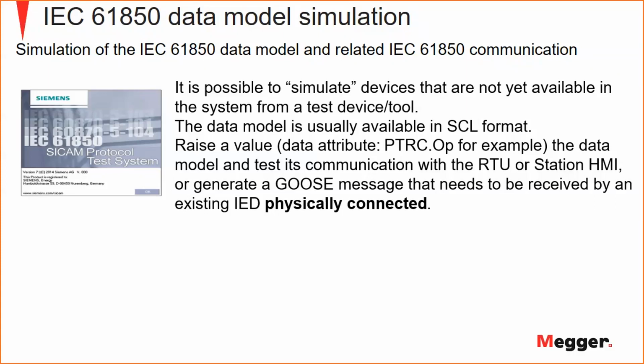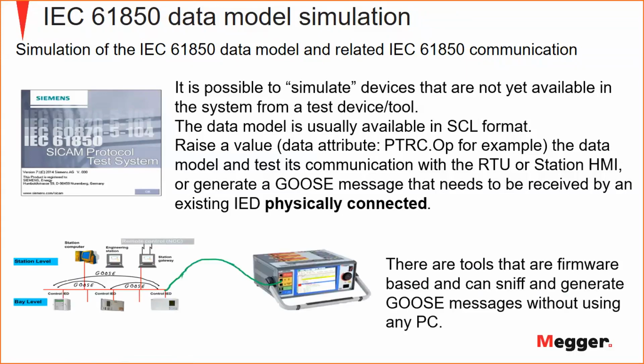So it's a signal for the trip. Could be a general trip, or could be some trip dedicated to some distance protection function, etc. So we can raise it without having the physical relay there. So we have software tools and we have hardware tools where we can also simulate a GOOSE message. We take the GOOSE message from the SCL file, we put it on the network, and we decide that we raise bit number 7 in the GOOSE message. Bit number 7 means trip. But there is no relay there physically that is tripping.